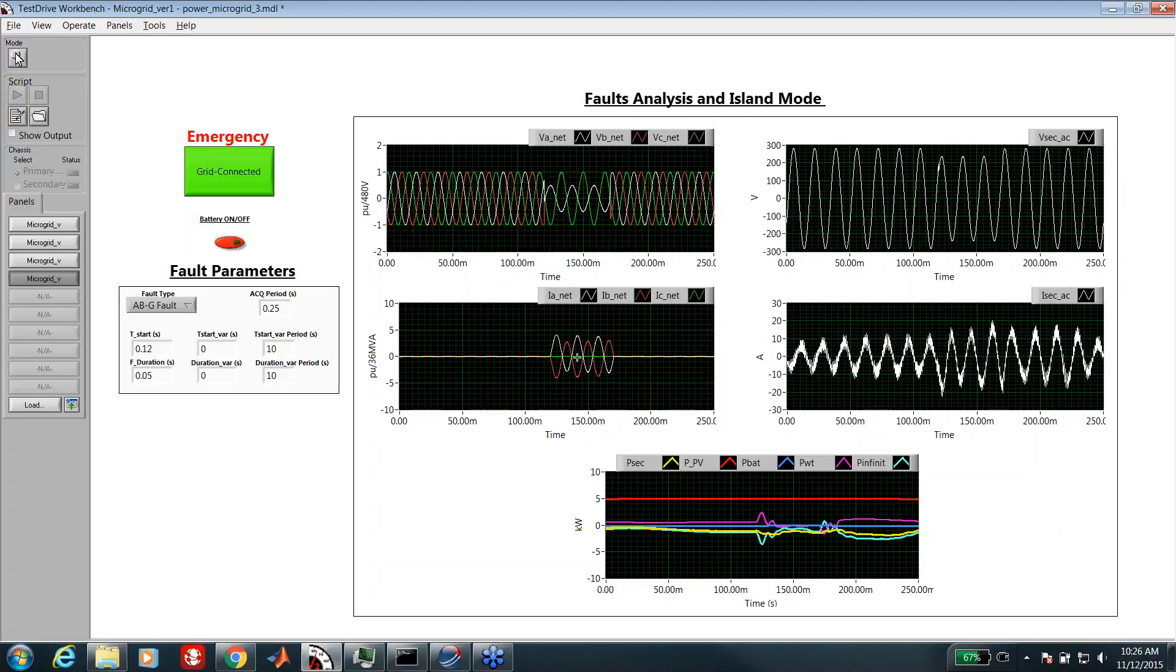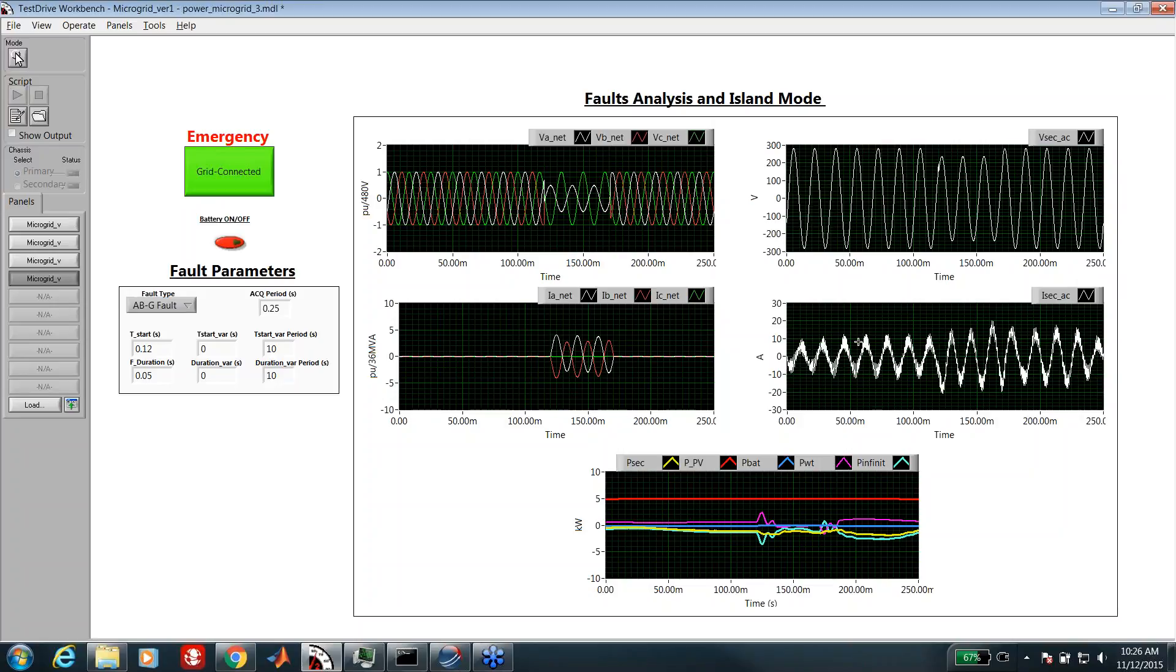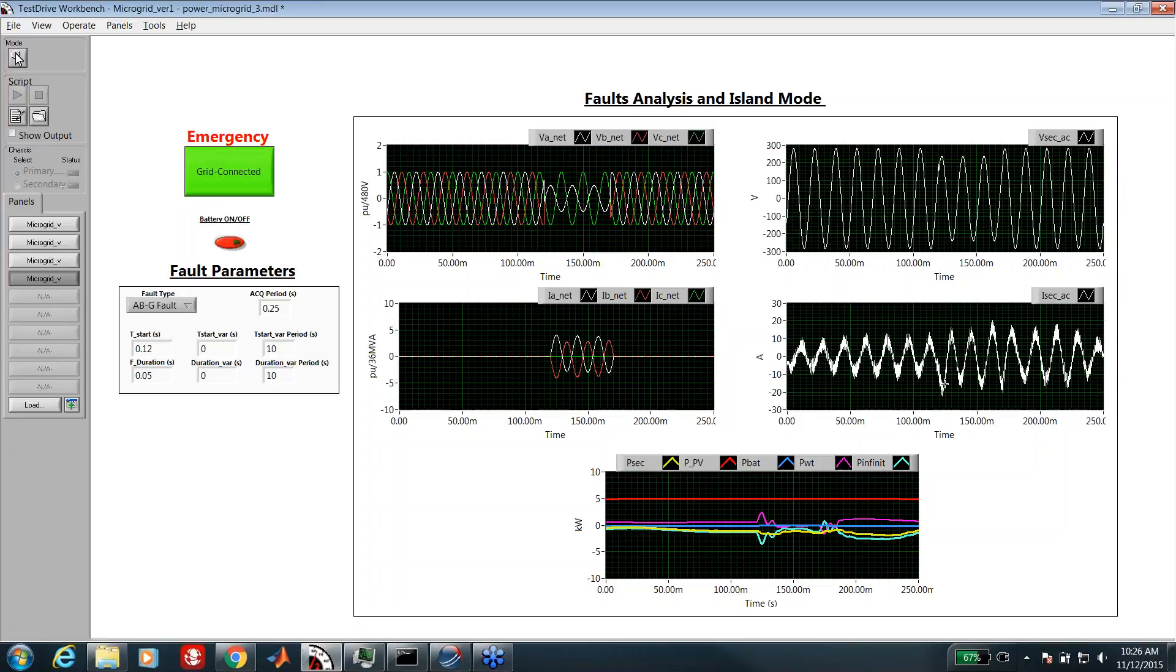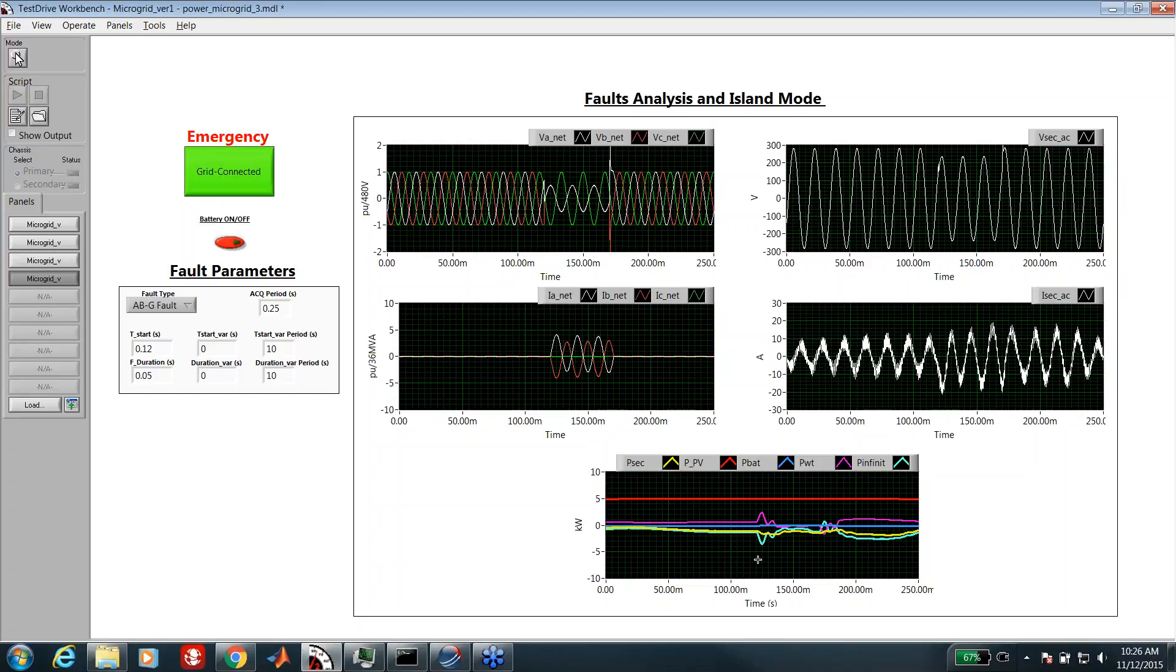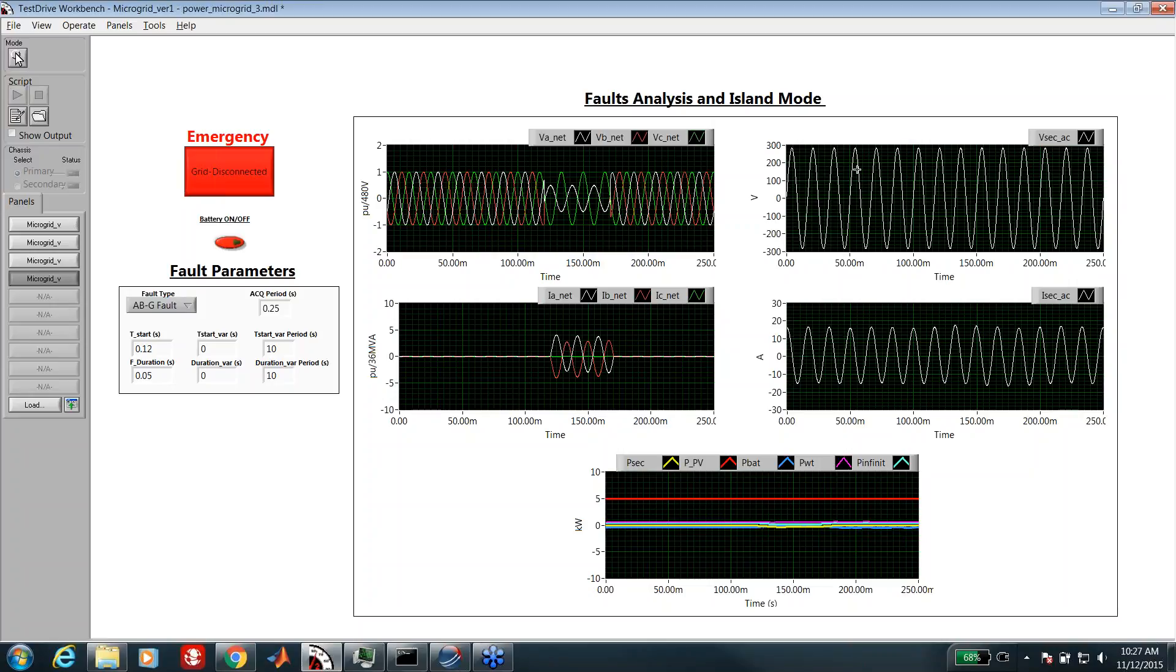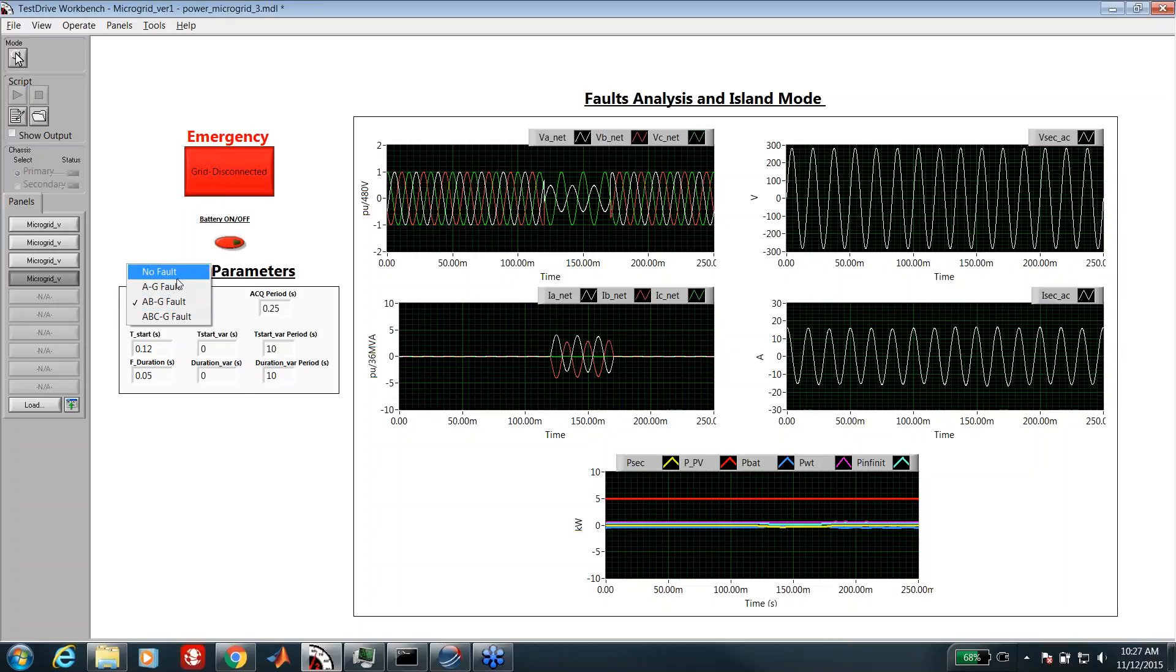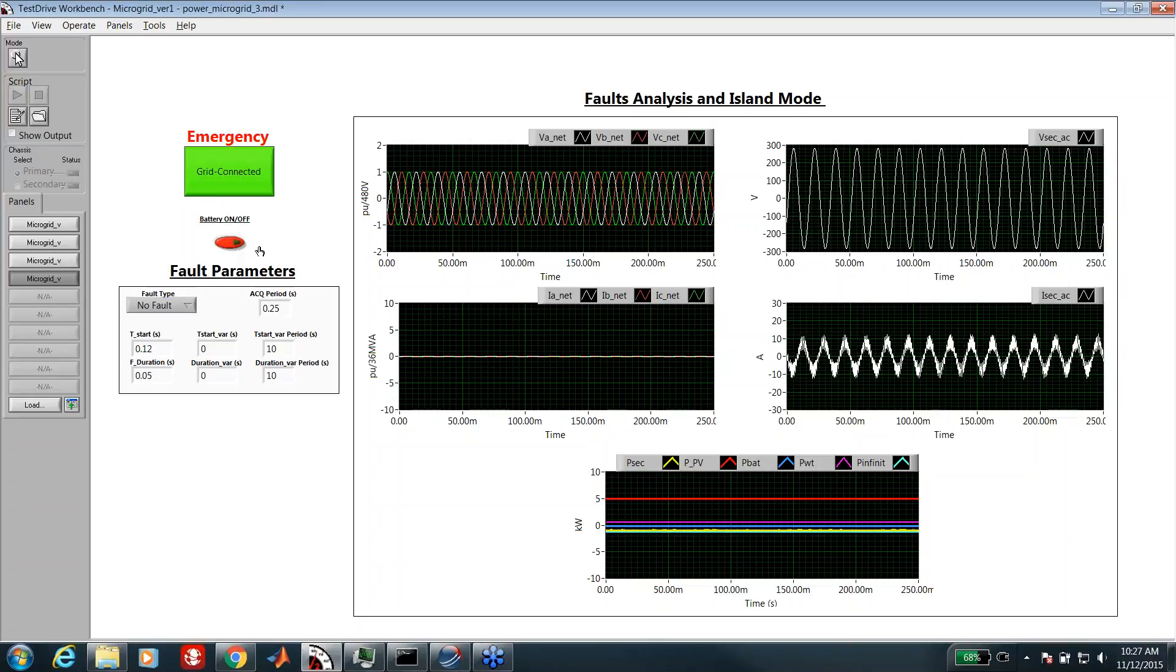This is the bus where the fault is applied. This is the voltage and current at that bus. Here we have the voltage, the AC voltage and AC current in the microgrid side. We can see clearly the influence of this fault on the microgrid by this voltage sag here and this fault current here. We can see it in the power graph also. What we will do is we can island completely our microgrid so we have no influence from the faults. Once we repair our fault, we can go back and reconnect to the grid again without any problem.